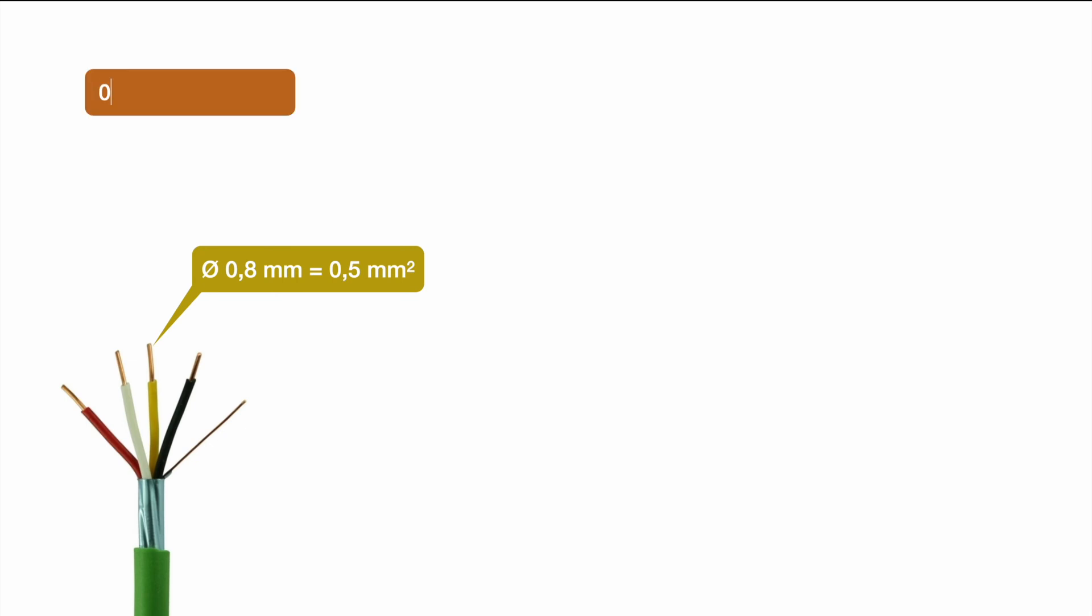To do so we will go with a simple example. For this we will assume we have this cable right here, it's a bus cable and the diameter is 0.8 millimeters which equals to 0.5 millimeters square. Since this is a copper cable we have to incorporate the specific resistance of copper which is 0.0171 ohm by millimeter square per meter.